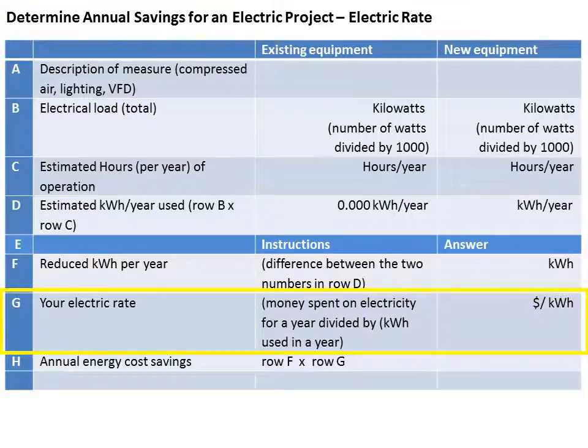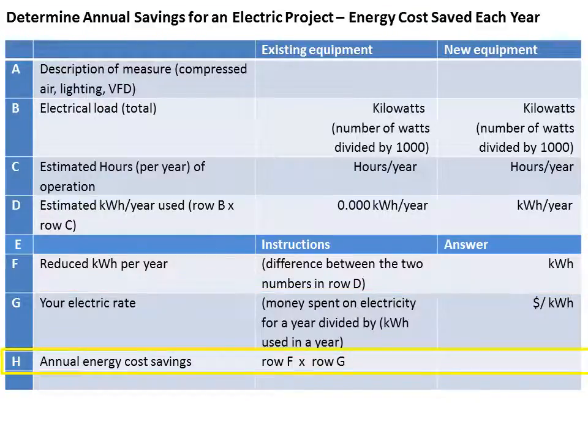Next, determine your electric rate by dividing the number of dollars spent on electricity for a year by the number of kilowatt hours used in a year. You will look at your electric bills to determine this information. We'll refer to an electric utility bill during our lighting project example. Now multiply your reduced kilowatt hours per year in row F by your electric rate in row G. This gives you your annual energy cost savings.